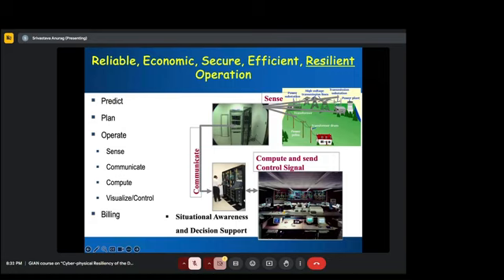The only way we know the status of the grid is by sensing, and sensing means we put a sensor. The most common sensor is a current transformer and potential transformer, or CT and PT, which come in different sizes and ratings. With that CT and PT, we can also feed information into the phasor measurement unit, or PMU, which is much faster, much more synchronized, and gives better high resolution data to analyze, especially when looking at dynamics.